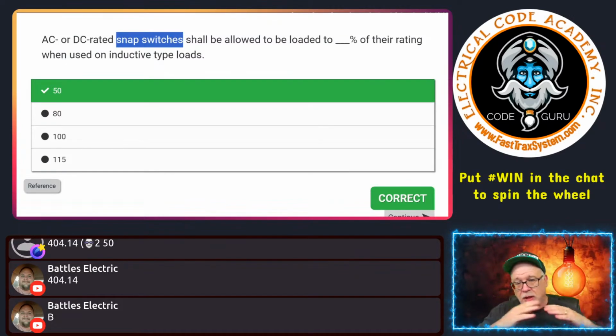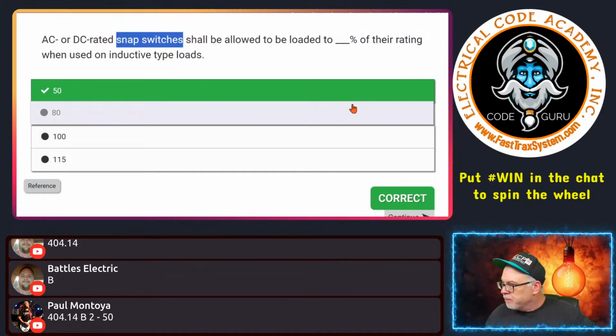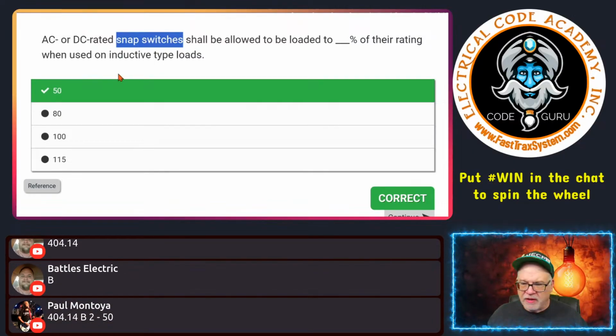So a 20 amp load, 50% of that would be 10 amps. On a 20 amp AC or DC snap switch that's being used for inductive type loads, you're going to have a limited load that you can put on that switch. That's what it's talking about. It's a percentage, okay? Does that make sense? Hopefully. All right, let's go to another one real quick.